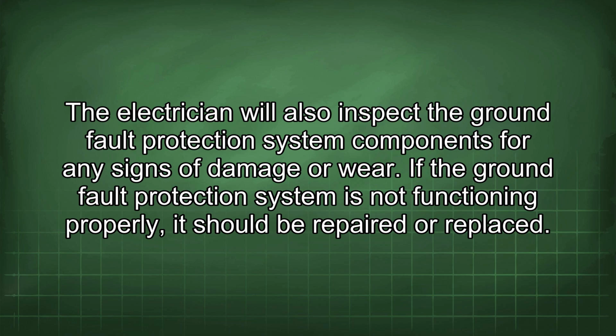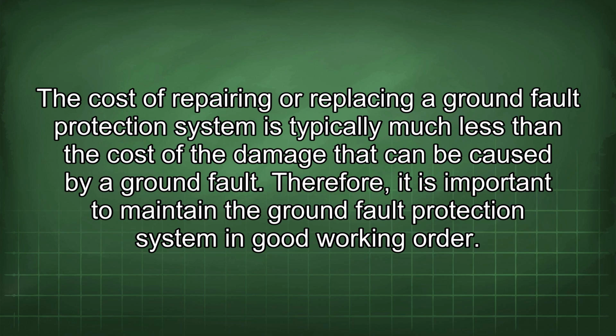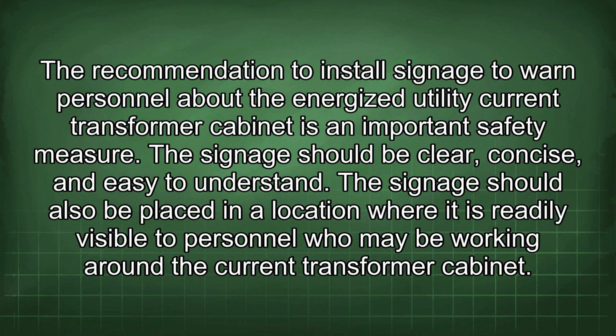The electrician will also inspect the ground fault protection system components for any signs of damage or wear. If the ground fault protection system is not functioning properly, it should be repaired or replaced. The cost of repairing or replacing a ground fault protection system is typically much less than the cost of the damage that can be caused by a ground fault. Therefore, it is important to maintain the ground fault protection system in good working order. The recommendation to install signage to warn personnel about the energized utility current transformer cabinet is an important safety measure. The signage should be clear, concise, and easy to understand. The signage should also be placed in a location where it is readily visible to personnel who may be working around the current transformer cabinet.